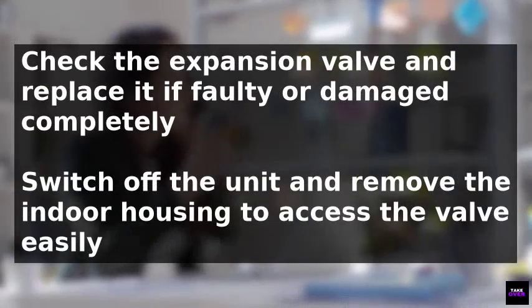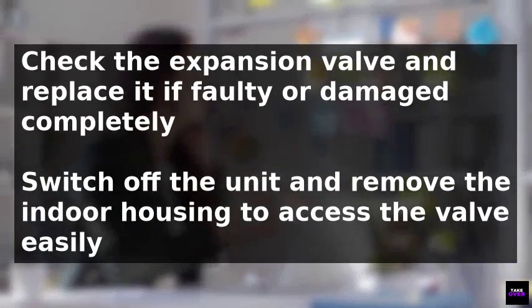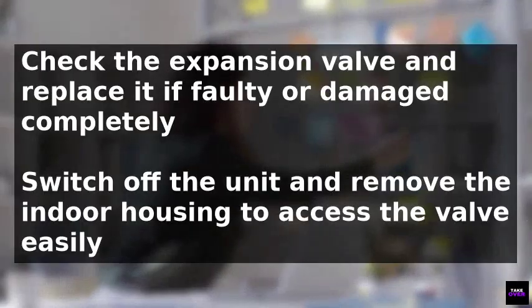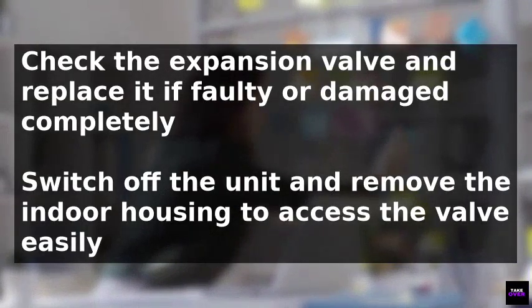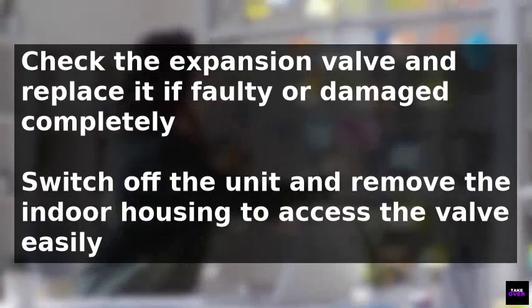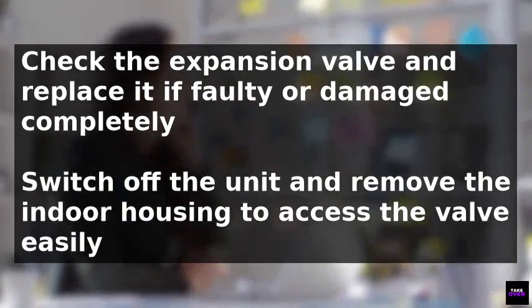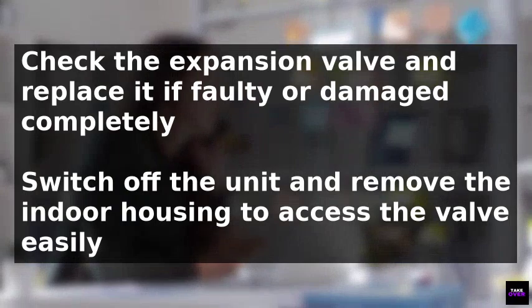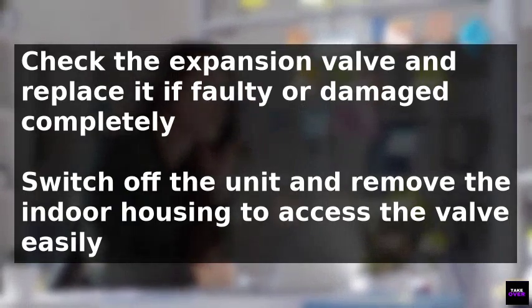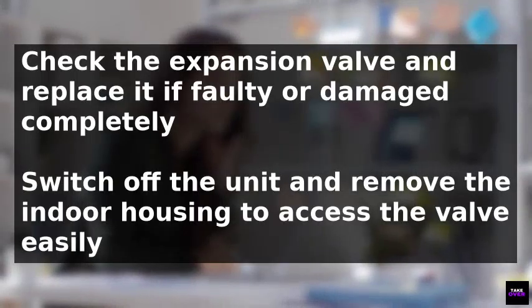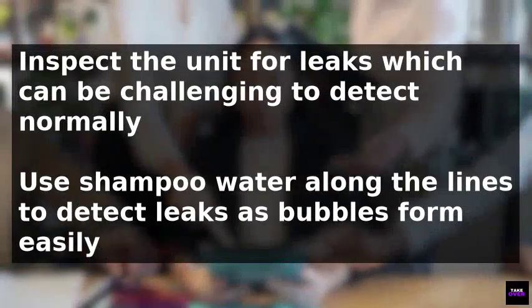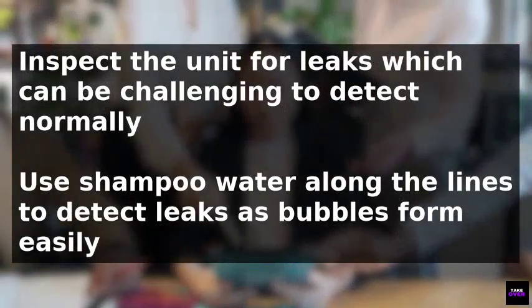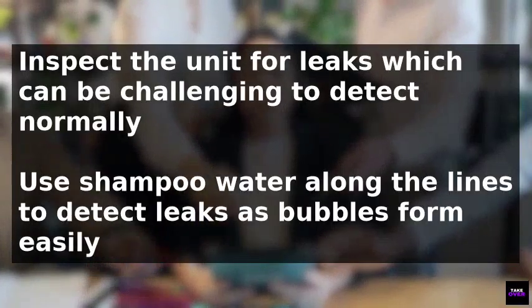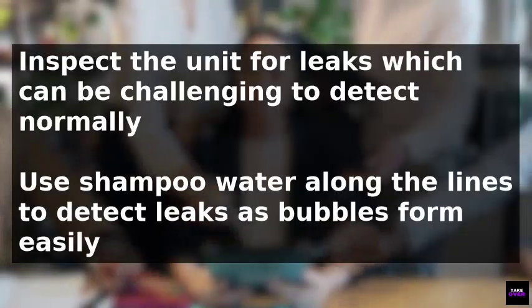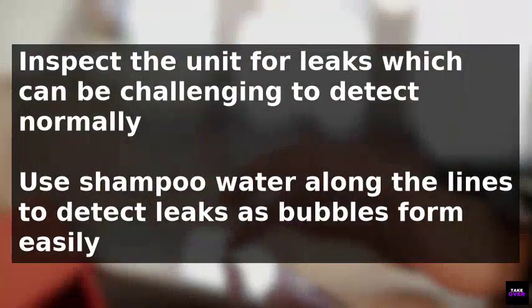If it's faulty, replace it by switching the unit off, removing the housing of the indoor unit, locking the refrigerant lines, and disconnecting the expansion valve from the evaporator coil. Then, remove the faulty valve and secure a new one in its place, connecting it to the evaporator coils. After unlocking the refrigerant lines and reinstalling the housing, switch the unit back on.